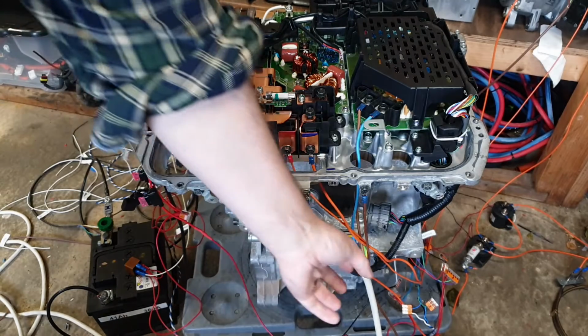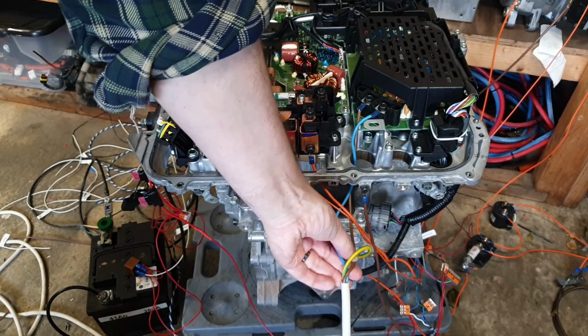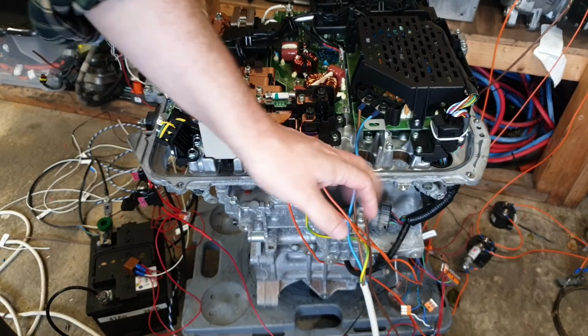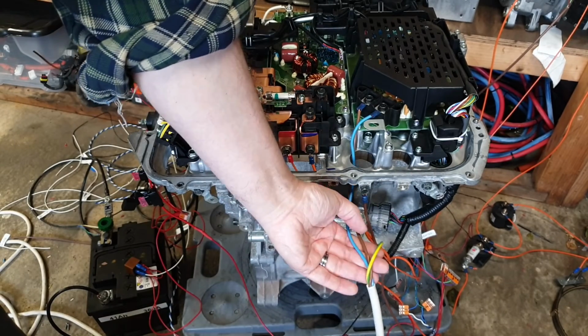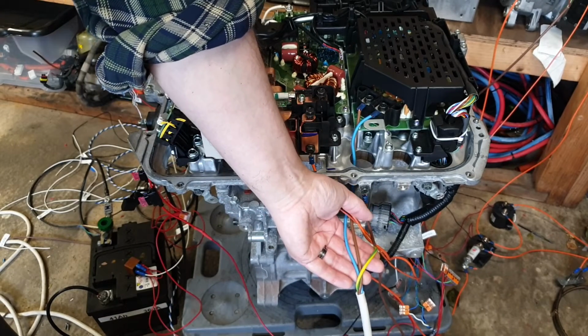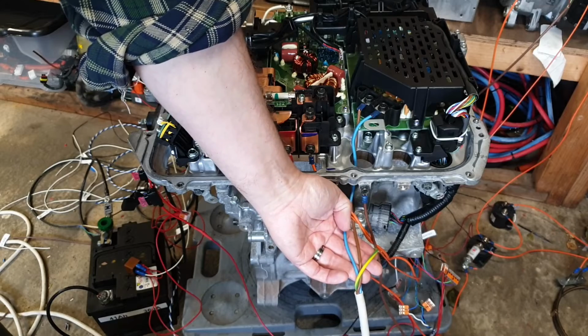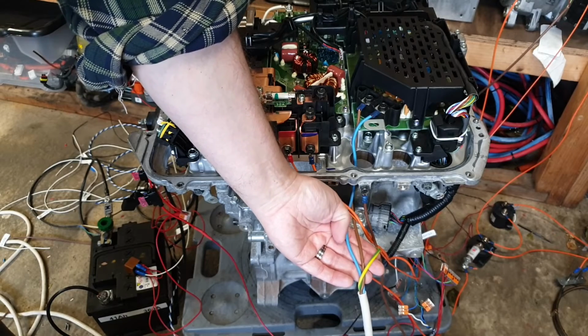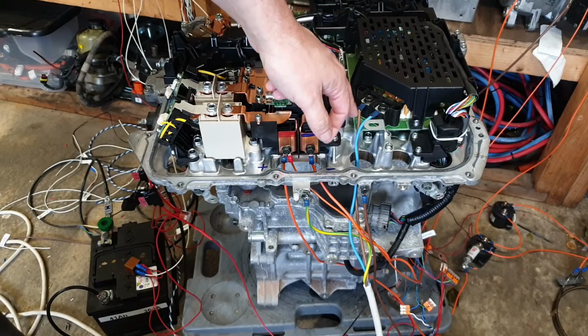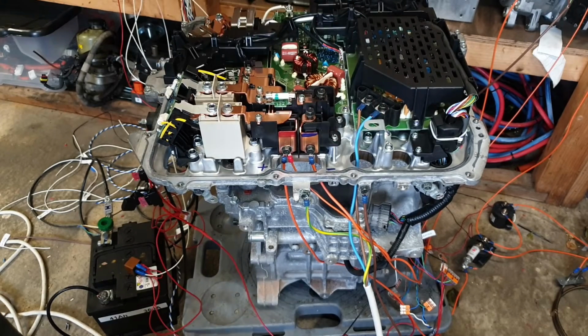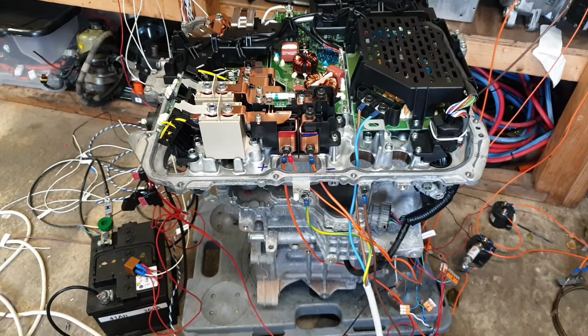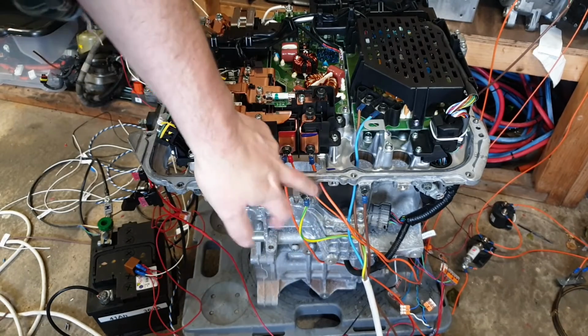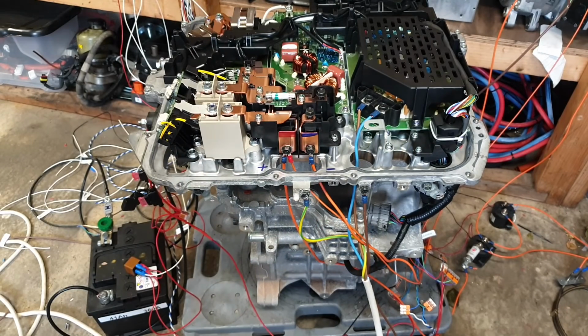So I've just got a piece of 3-core cable here. This is a single phase 6 kilowatt charger. Green and yellow is earth or ground, brown is our live or hot, and blue is our neutral. We connect the live and neutral to their relevant terminals here in the PDM, and we connect earth or ground to our chassis, at a convenient location.